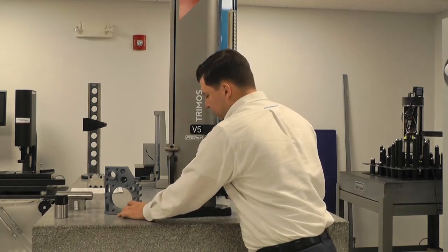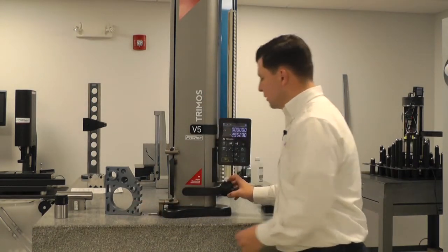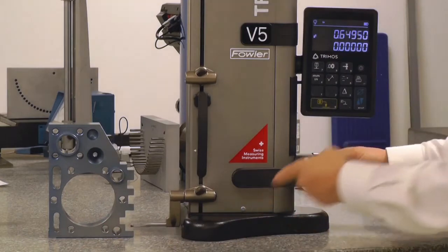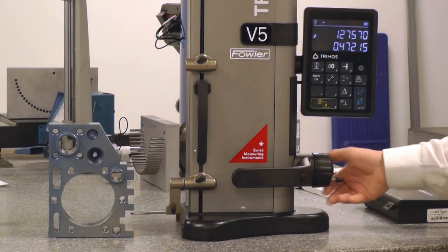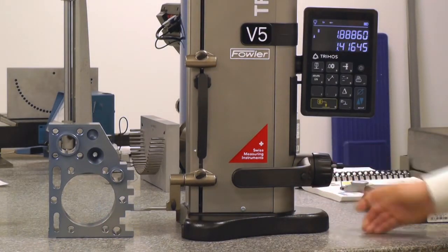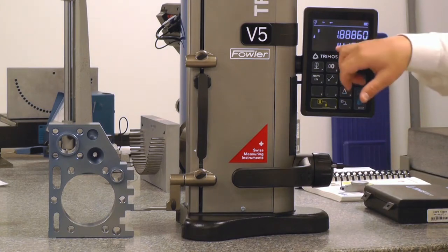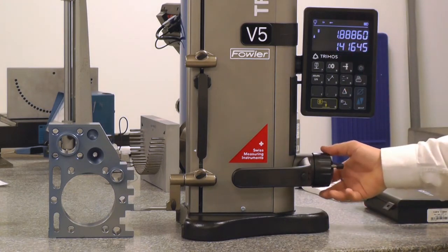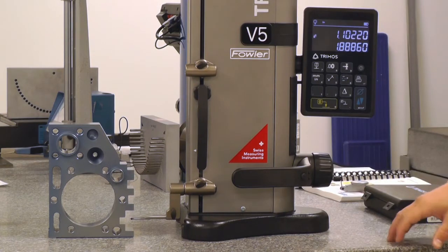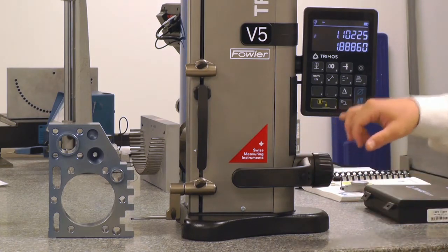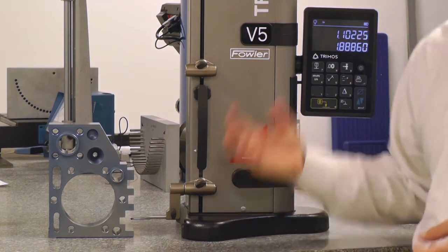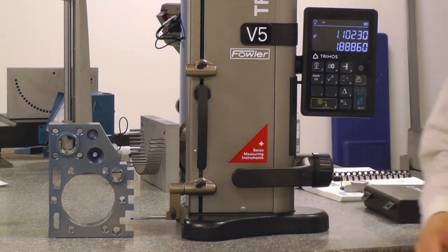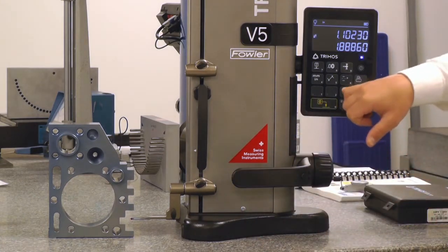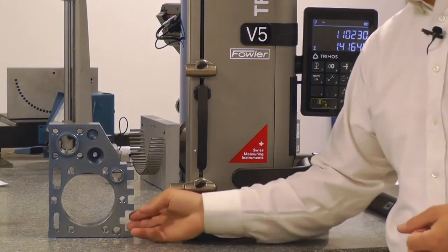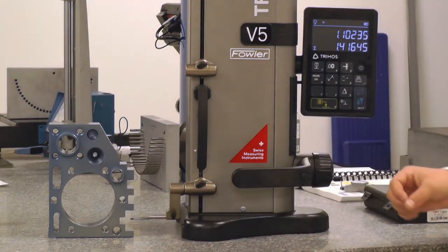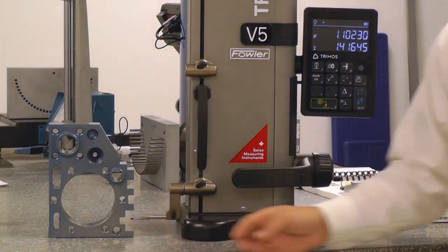Let's go back and replay this one measurement here. Come back to 0, measure this land, and then measure the high side. Again, 1.888, and then 1.416. If we release that contact, and if we want to know the difference, my delta key here is always going to recall the difference between the last two measurements. So if I hit the delta key, that's recalling this difference feature. So we've calculated that slot width.